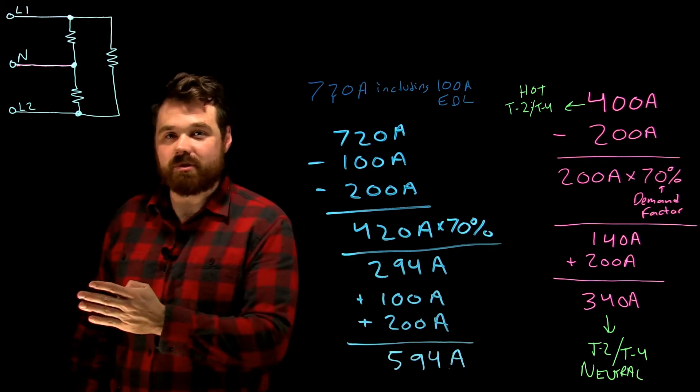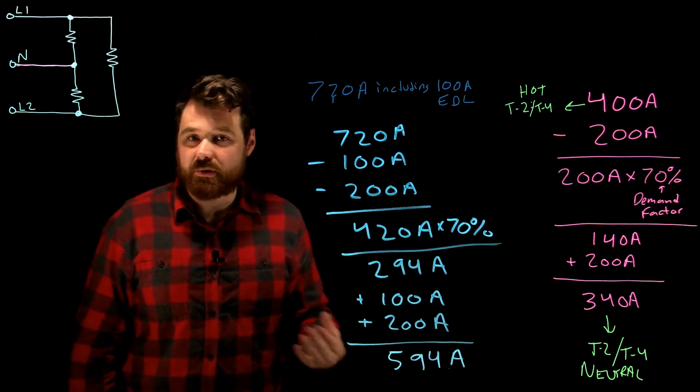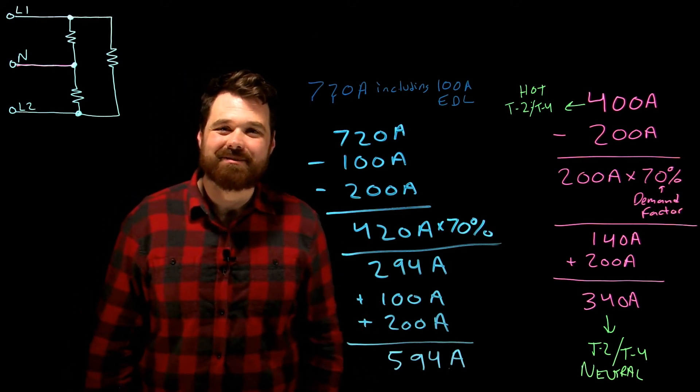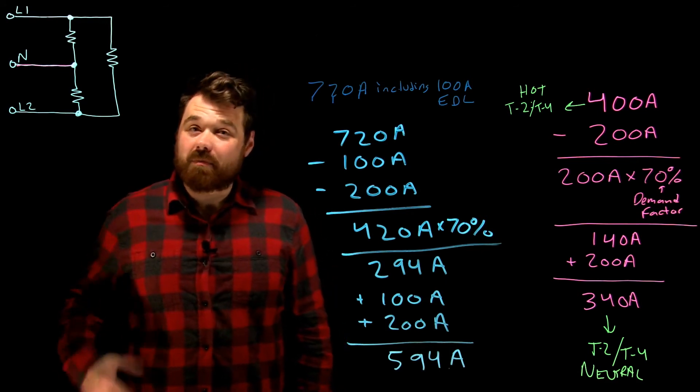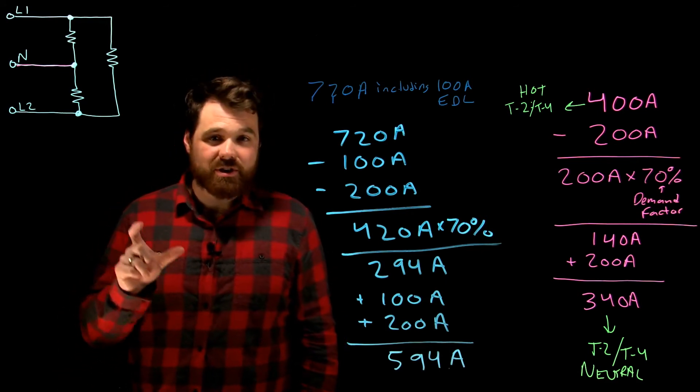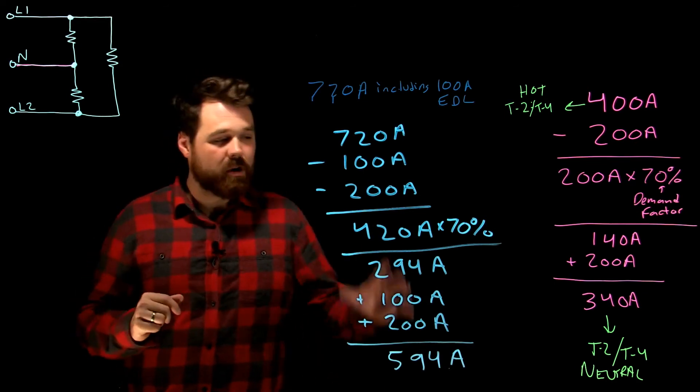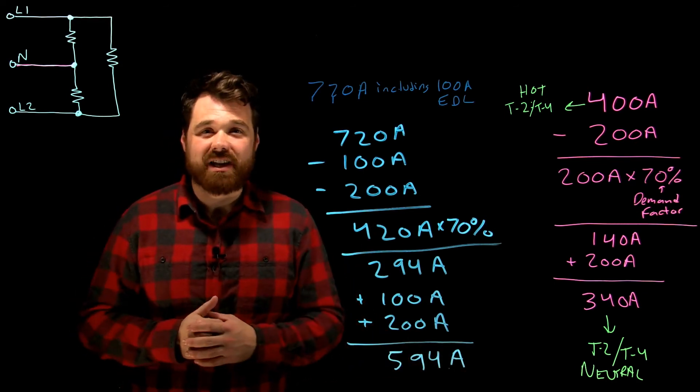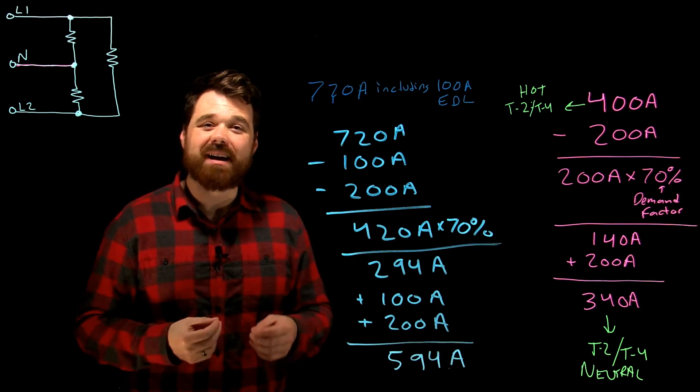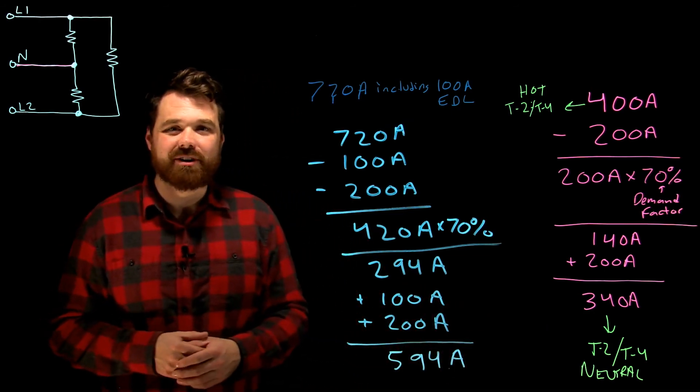And then of course, using tables 8, 9, and 10 to size my conduit because not all the conductors are the same size. Make sure you're referencing your code book for this. There's a couple other little sub rules that are going to come into play. But for the most part, this is your basic neutral sizing calculation to figure out the required ampacity of the neutral conductor. Thanks for watching.